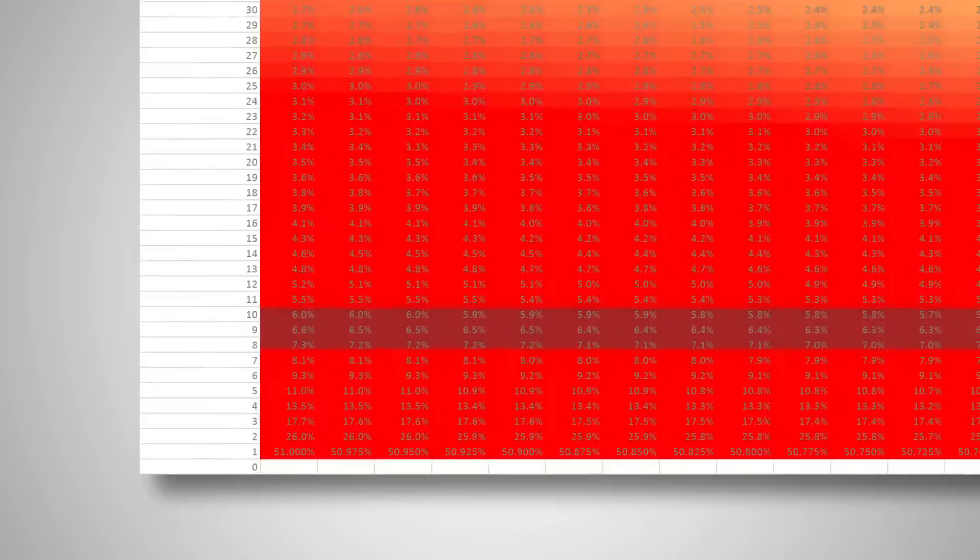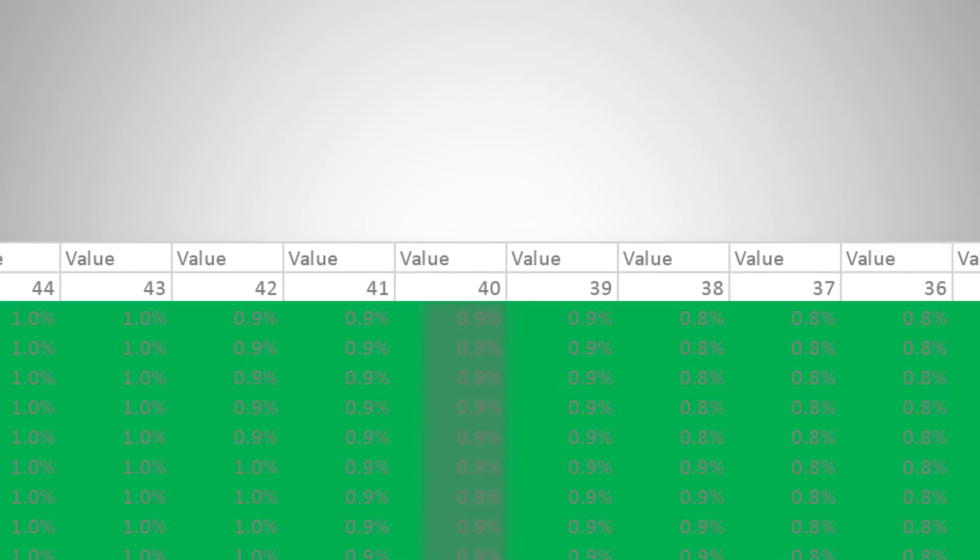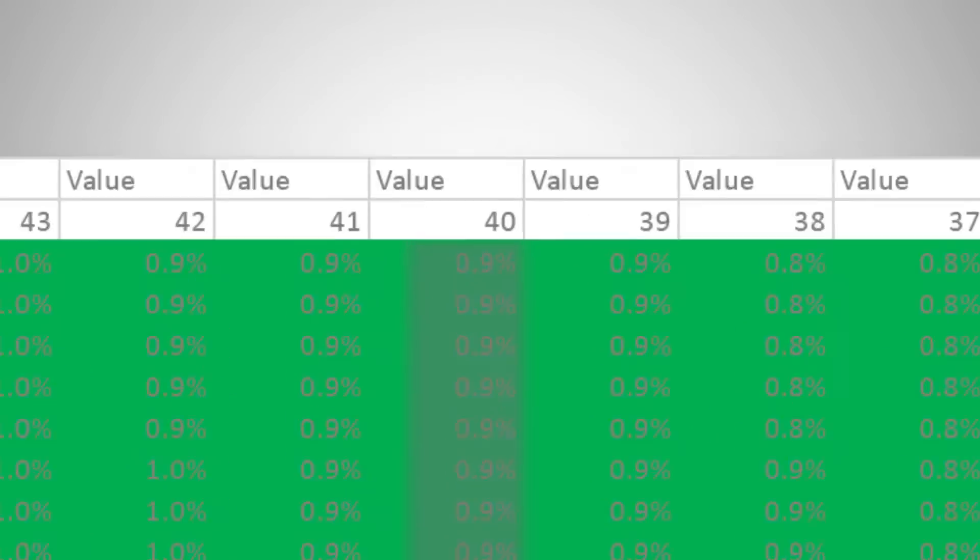And this data point at 9 percent of full scale and 40 degrees Celsius reveals we are in the deep red color, registering a significant 5.9 percent allowed error.